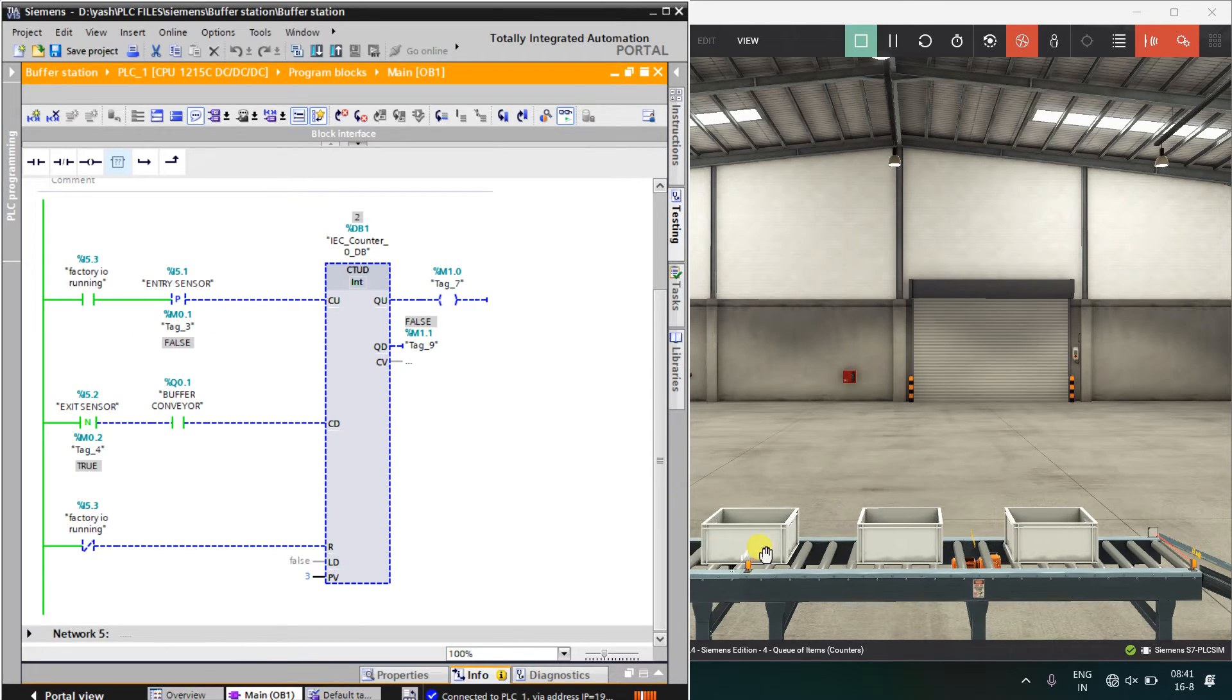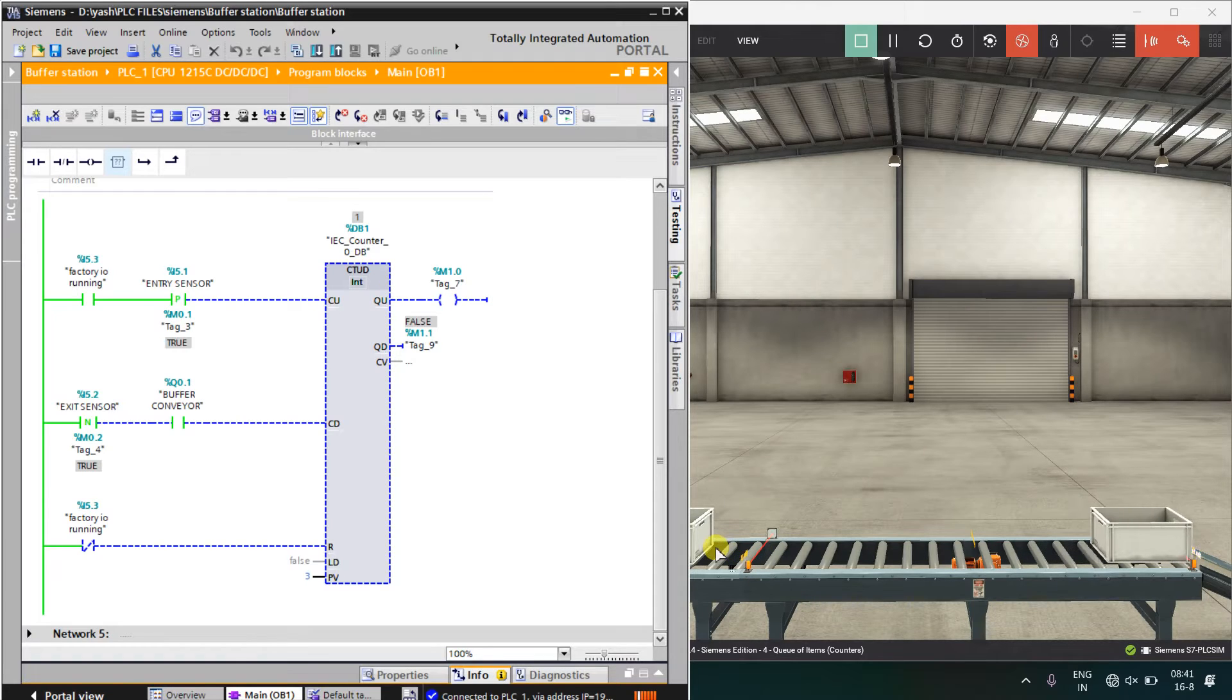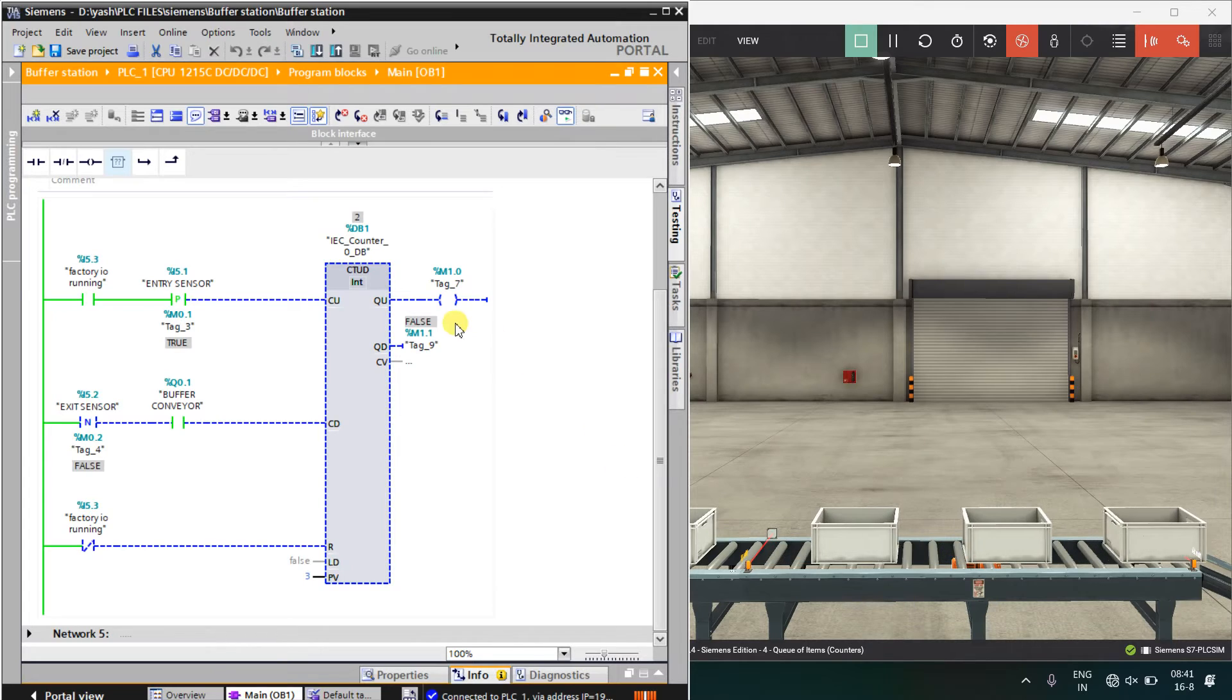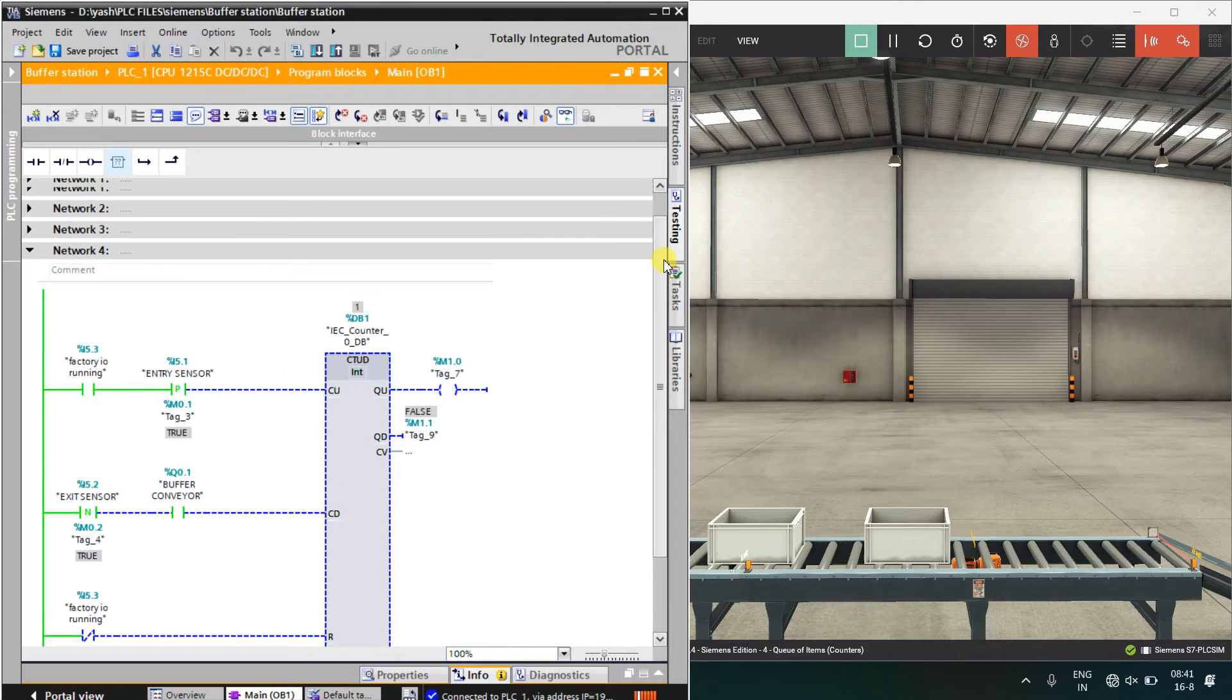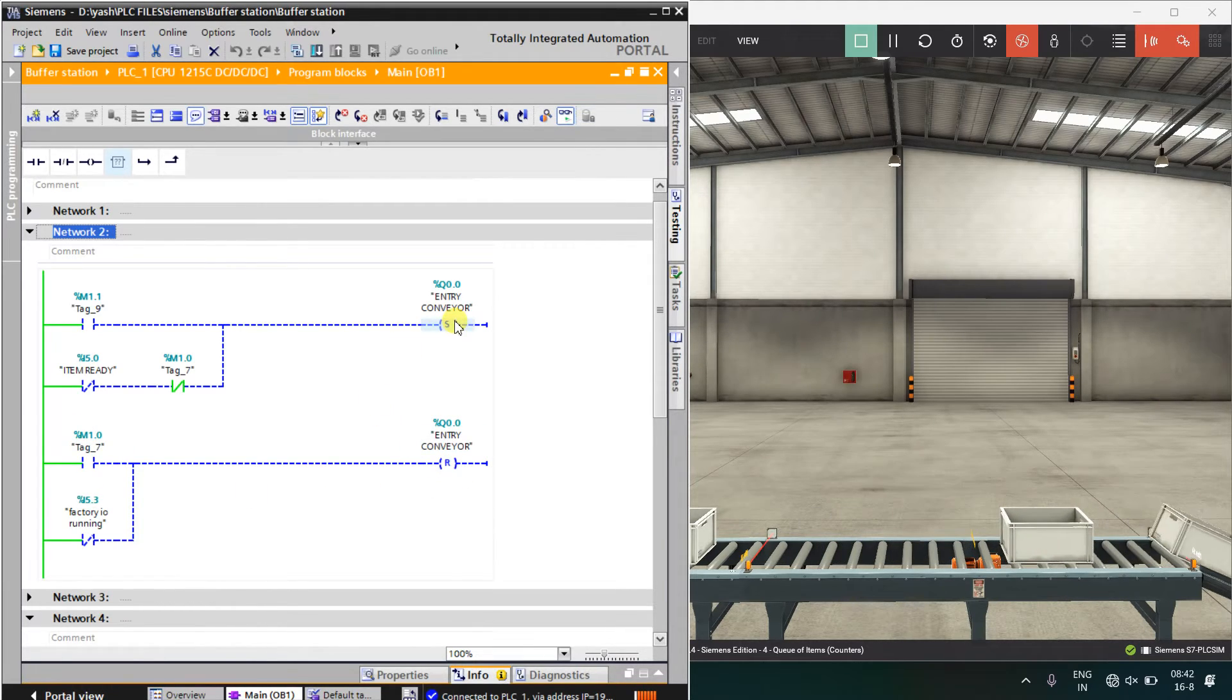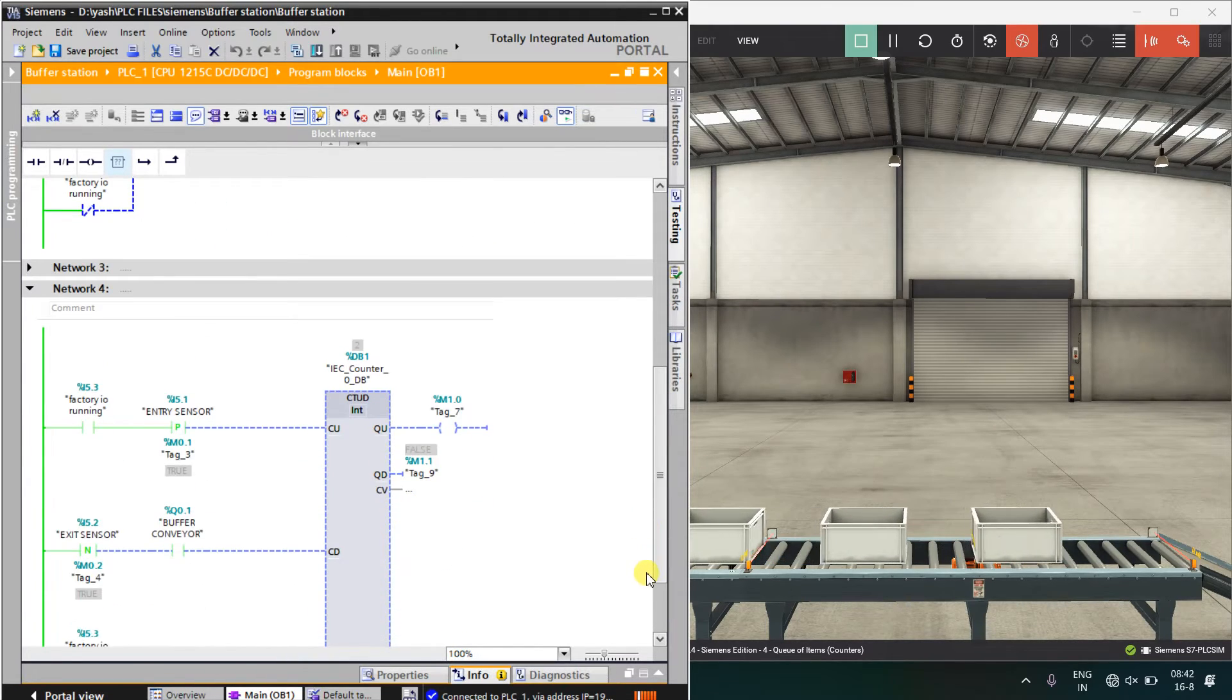As soon as the box will pass over here, it will count up. When the box comes and the box leaves, there will be positive triggering. I have taken the positive pulse of the entry sensor, means the box passed through this sensor and the factory IO was running, then it will count up. And finally, when the count up is done, that means this bit is on. What should happen? When the count up is done, entry conveyor should be reset and it should not set again because box will be there but it should not set again. That is the first function.